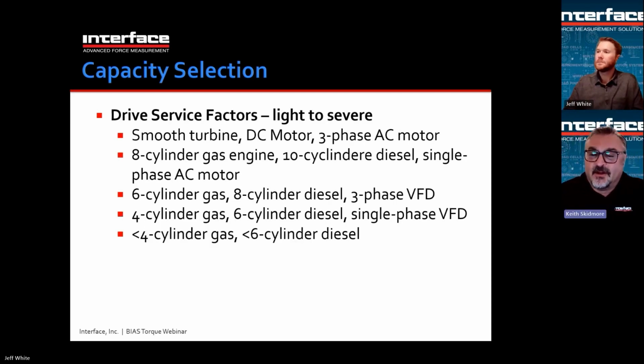So, drive service factors, from light to severe. As in spinning a smooth turbine, it spins smoothly. There aren't any pulsations. Our DC motor and three-phase AC motor spin and create torque in a smooth manner. A little more severe, but not bad, would be something like an 8-cylinder gas engine or a 10-cylinder diesel, or a single-phase AC motor. They spin quite smoothly. And the 6-cylinder gas or 8-cylinder diesel or 3-phase VFD motor, a little harder. And then 4-cylinder, you kind of get the trend here, 6-cylinder diesel, a single-phase VFD.